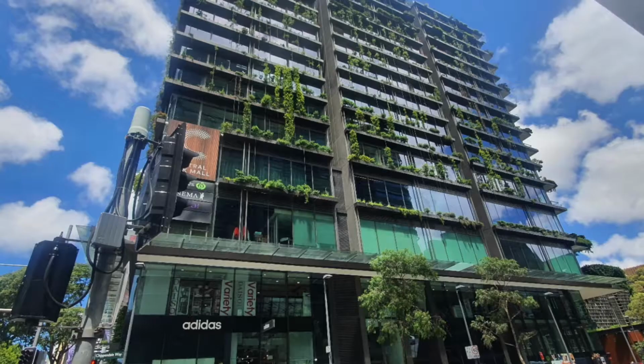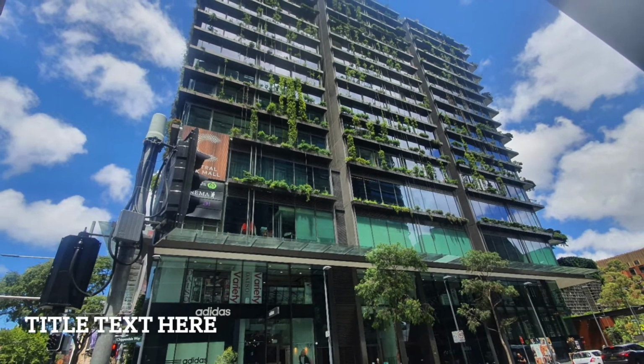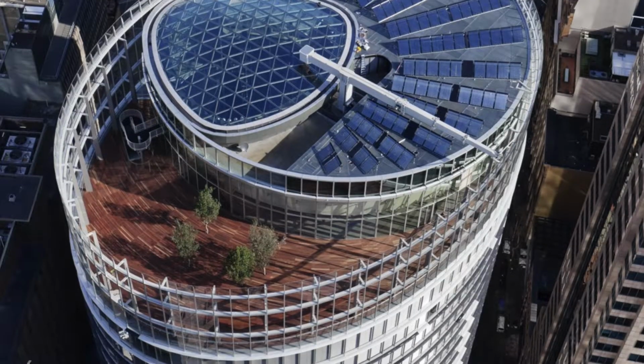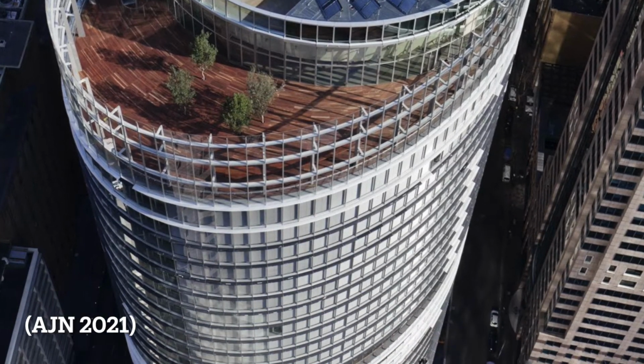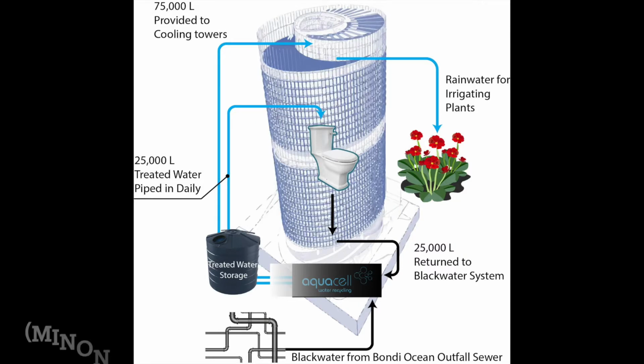Two precedent buildings looked at for alternative water supply were both similar in recycling all water usage, including black water on-site treatment. 1 Bligh Street recycles all water and harvests water from the Bondi Ocean outfall to recirculate treated water through the building with separate colour-coded plumbing system. The separate system prevents cross-contamination and supplies toilet flushes, cooling towers and plant irrigation.